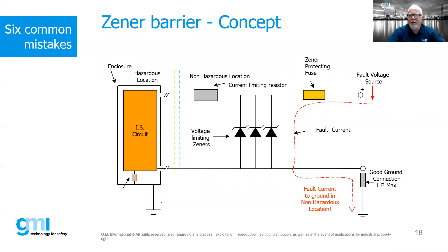The important thing to note here is that when we use a Zener barrier, we must have a good ground connection. That is separate. That is called our clean earth, if you will. That's separate from our normal earth. So it's imperative that we do have a good clean ground to be able to allow that fault current to dissipate, if you will.